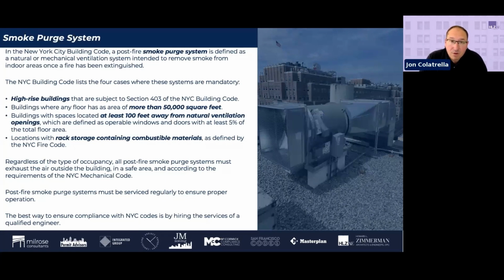But very, very important to note, our office does quite a bit of existing building retrofits. Going along with that, we had a particular situation where we were retrofitting a fire alarm system in an occupied residential building. As part of doing that, one of the stipulations for this building owner fell in with doing a post-fire smoke purge system on a 100-plus-year-old building. So just something to keep in mind. It doesn't always just have to be on a new building. Certainly a major existing high-rise building going through a major alteration is likely going to have to install one of these ventilation systems as well.